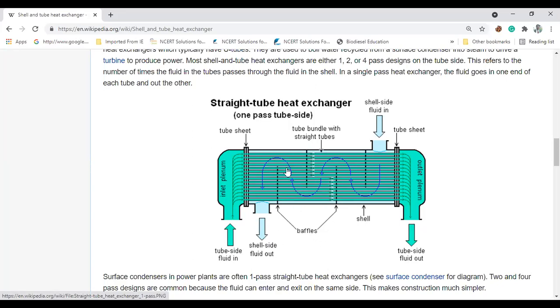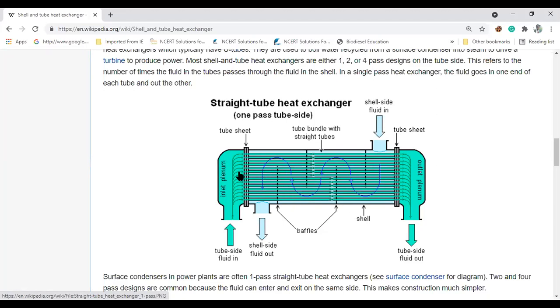If there is a failure of the shell, the entire fluid will spill on the floor, causing damage to property and people. Also, high-pressure tubes are cheaper than a high-pressure shell, because the shell requires a large quantity of material. Always keep high-pressure fluid on the tube side because high-pressure tubes are relatively cheaper than the shell.